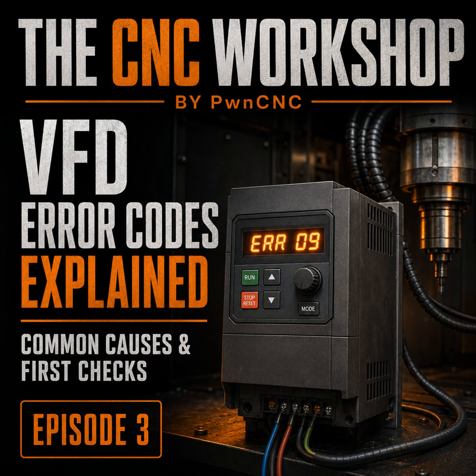Yes. Combine the code with the timing, cutting load, machine movement, cable condition, and unloaded behavior. That combination is much more reliable than the code alone. And please resist the urge to solve every electrical problem by changing a parameter you found in a forum post from 2017. Especially when it was written for a completely different VFD. Record the original settings, use the correct manual, and change only what the documentation for your controller and VFD requires.